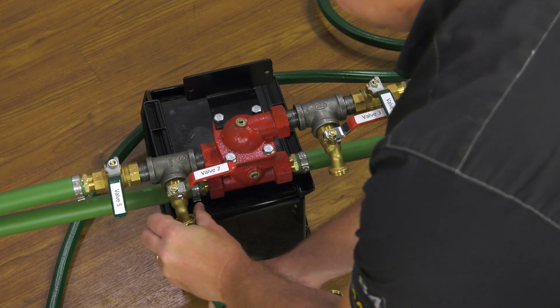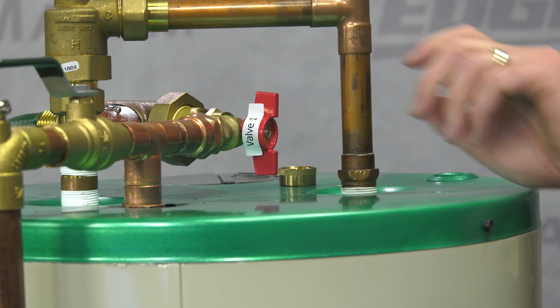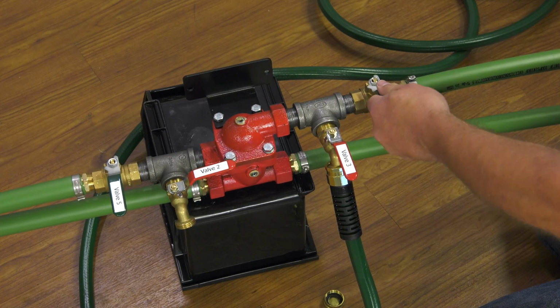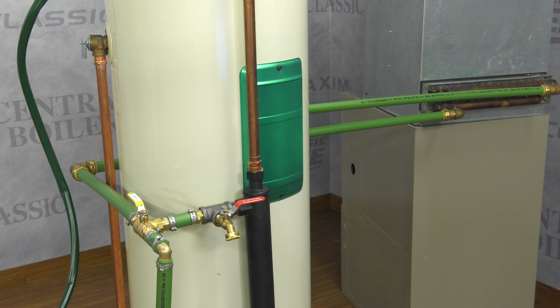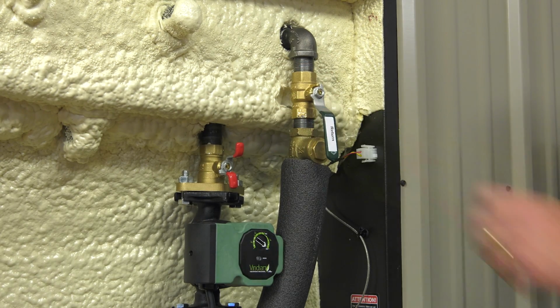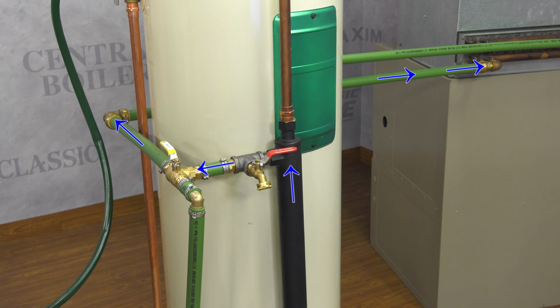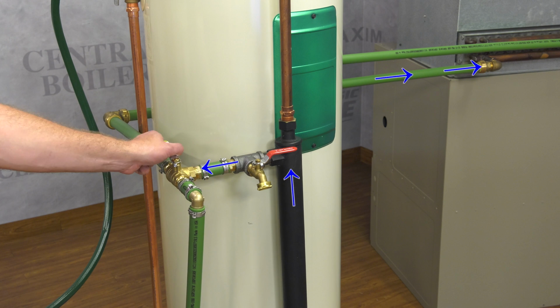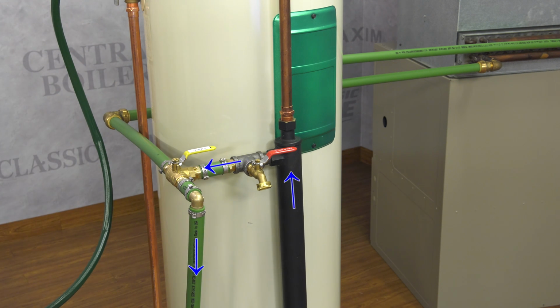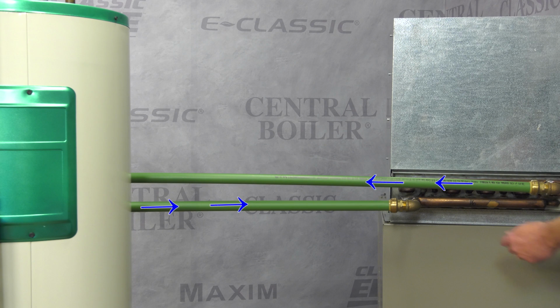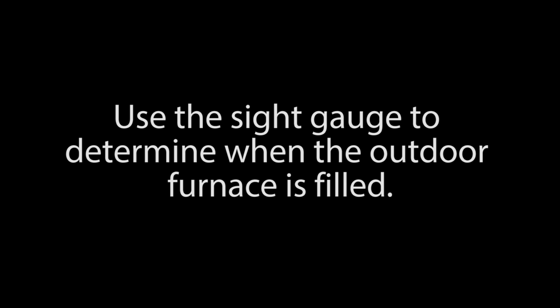Move the garden hose from valve 2 to valve 3, then open valves 1, 3, and 4. If your system has a seasonal manual bypass valve, make sure valve 6 is positioned to direct water through the heat exchanger first. Next, open the valve on the return line of the outdoor furnace. If your system has a seasonal manual bypass valve, turn valve 6 to the bypass direction for 30 seconds. Then turn the valve back to the previous position. The heat exchanger manifold and fittings will become cold as the water flows through the heat exchanger to the outdoor furnace. Use the sight gauge to determine when the outdoor furnace is filled.